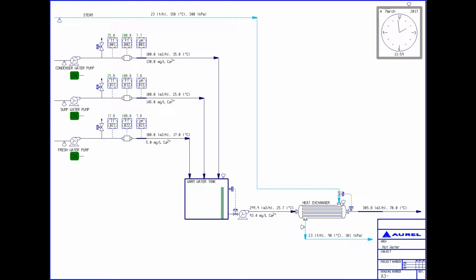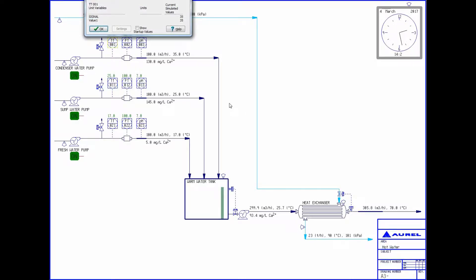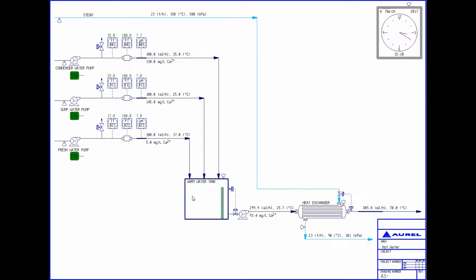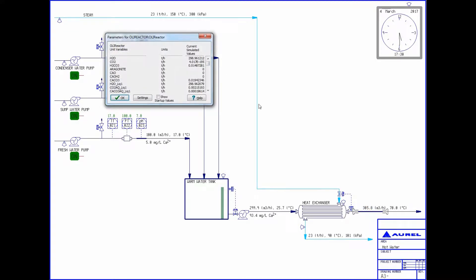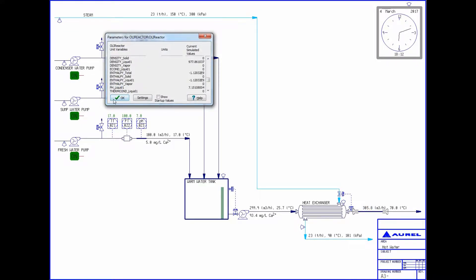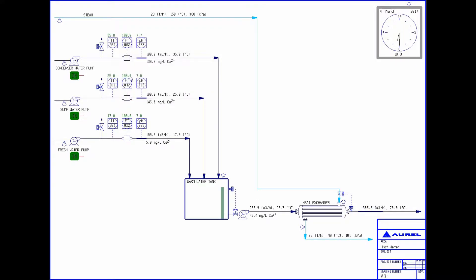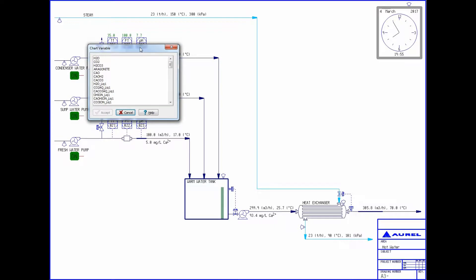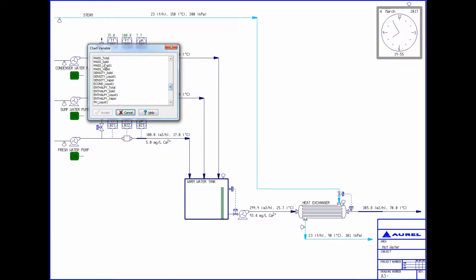As the simulation runs, you can select a sensor and see what values it is reporting. The water streams enter a tank, mix, and then are pumped to a heat exchanger where the water is heated up to 70 degrees Celsius. I have set up an OLI reactor after the heat exchanger which is given the composition of solution leaving the heat exchanger at its new temperature. We will use this to predict if scale is going to form through the heat exchanger by watching if solid is predicted to form by the OLI calculations.